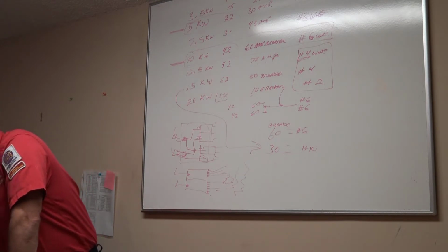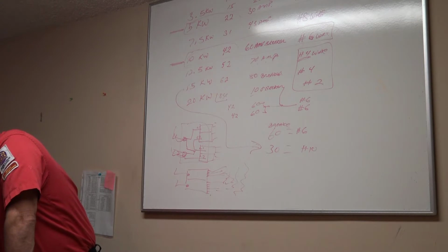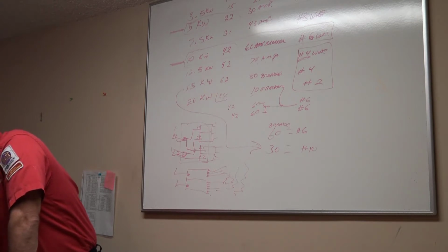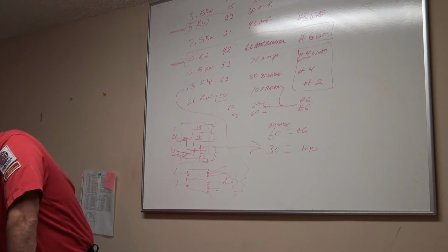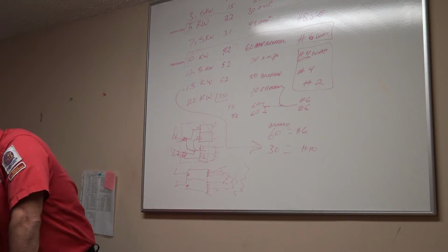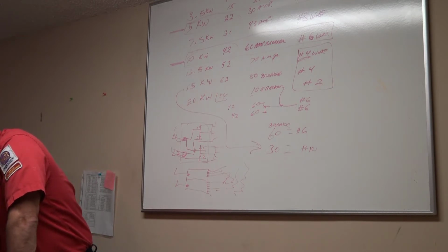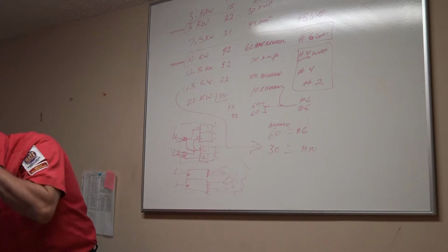Is it mounted properly and secure? Is it okay? Does it work fine? Is it bad, not sending voltage to the fan relay and other components? Is it miswired? The wires are not in the correct location, causing malfunctions. If that's the case, look at the wiring diagram and hook them up correctly and make it run properly.